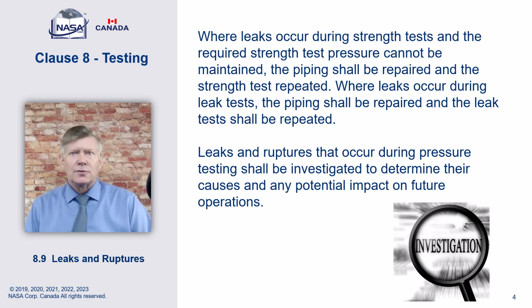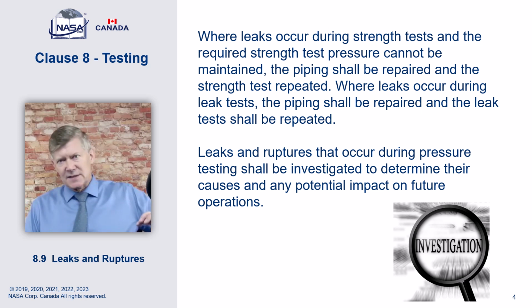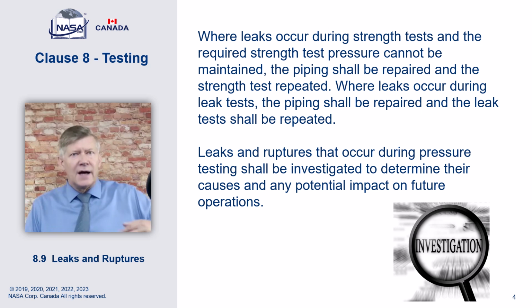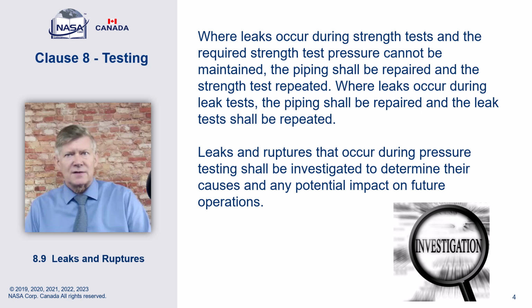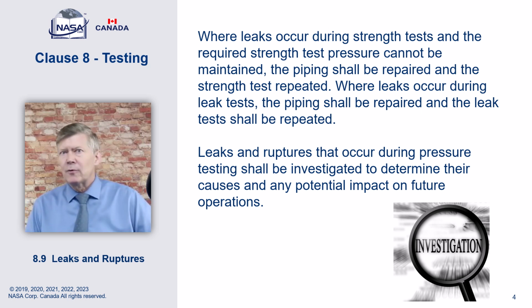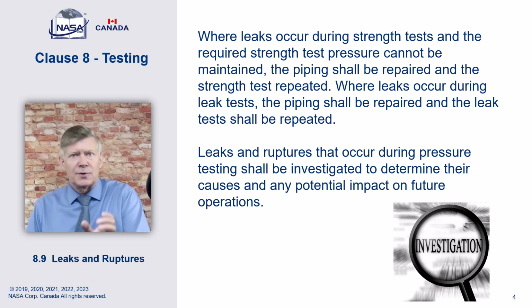Now, where leaks occur during strength test and the required strength test pressure cannot be maintained, the piping shall be repaired and the strength test repeated. Where leaks occur during leak tests, the piping shall be repaired and the leak test shall be repeated. Now, this is very much in conjunction with the clause we looked at earlier, identifying the intent that we're not to be doing cyclic testing, especially on the strength test. So the wording here is very important. Where the leaks occur during the strength test and the strength test pressure cannot be maintained, we will repair it. But if you have a leak during a strength test and you're able to maintain the appropriate test pressure range, the strength test pressure range, you keep that test going. Okay. Leaks and ruptures that occur during pressure testing shall be investigated to determine their cause and any potential impact on future operations.